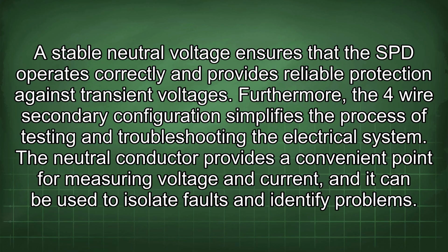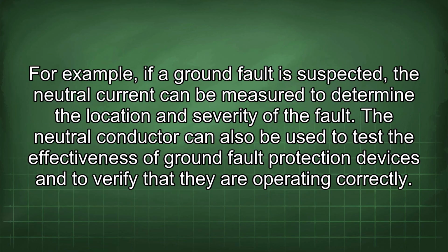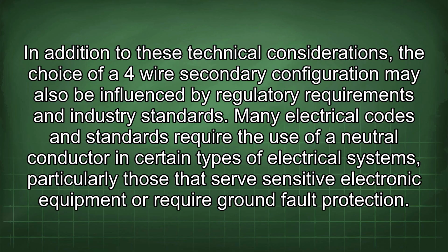The neutral conductor provides a convenient point for measuring voltage and current, and it can be used to isolate faults and identify problems. For example, if a ground fault is suspected, the neutral current can be measured to determine the location and severity of the fault. The neutral conductor can also be used to test the effectiveness of ground fault protection devices and to verify that they are operating correctly.